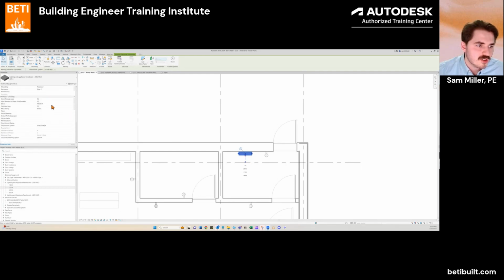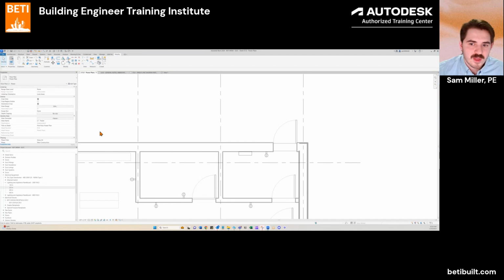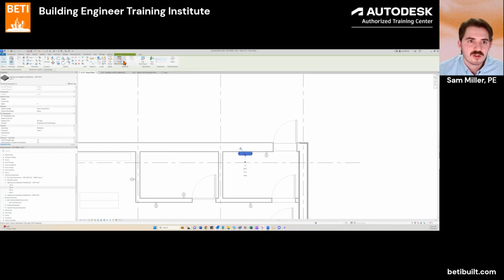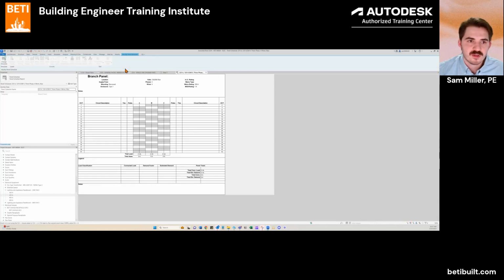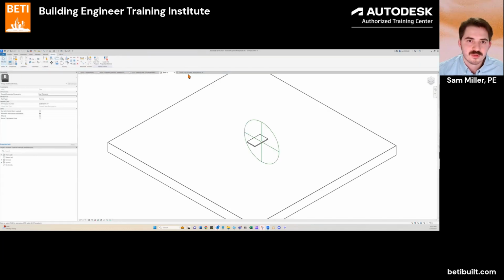And then you can click that. You can see all of the parameters associated with your panel board. And then to create a panel schedule, you simply go click the panel. It'll bring up this modify electrical equipment tab. You can click create panel schedule, use the default template. And now you've got a panel schedule associated with that panel that you put down.